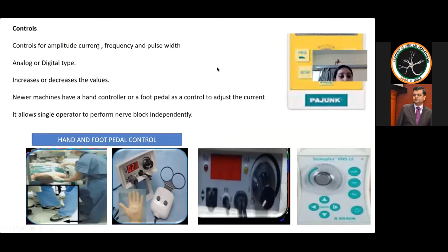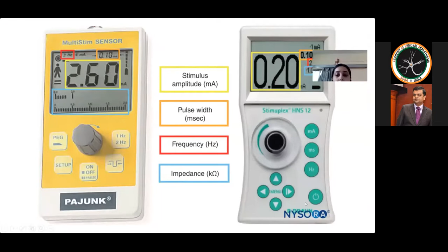Coming on to the control, there are three sets of control on the nerve stimulator, that is current, frequency, and pulse width. They may be of analog or digital type, and each control increases or decreases the value of the control parameter. So you can see here the newer machines have a hand controller and foot pedals, which allows the operator to perform the block independently. Now, as you can see here in the picture, the yellow box shows the stimulus amplitude. The orange box shows here the pulse width in milliseconds. The red box shows here the frequency in hertz, and the blue box shows here the impedance in kiloohms. You can get it in Pajunk and in Vygon machine.